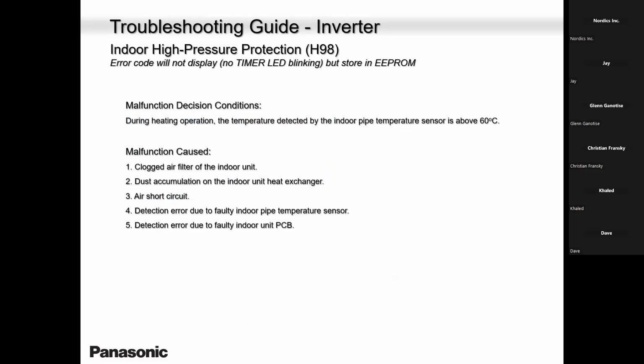Okay, so indoor high pressure. Keep in mind, guys, anytime the indoor unit is throwing a high pressure alarm or high pressure protection, we know definitely you are in heat mode. Because when you are in heat mode, the indoor becomes your high side and your outdoor becomes your low side. So anytime we have H98, it could be a clogged filter, a clogged blower wheel, and stuff like that.